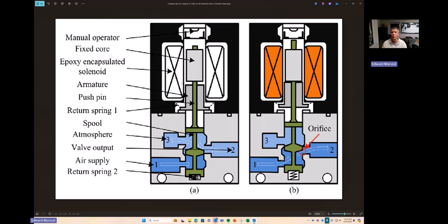Furthermore, who provided the coil? Maybe one company is using 100 rounds where a different company is using 1,000 rounds. The company that uses 1,000 rounds, that coil is going to have a much lower failure rate because it's designed more stoutly. Another item that can cause a failure here is this spring.